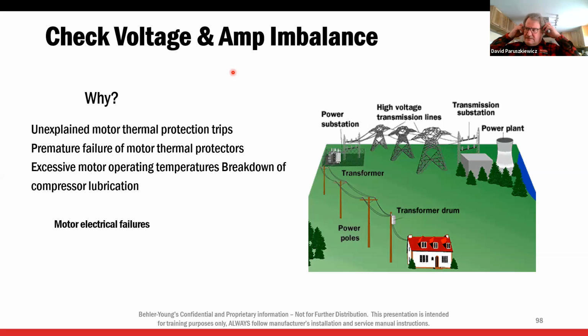Okay, so voltage and current imbalance. Now this, again, like I said, used to be we checked voltage and we're good, right? We got voltage. But with all the electronics, VFDs, ECM motors, economizer modules, voltage imbalance is going to lock things out now. If we have a bad voltage imbalance, the VFD can lock itself out. That ECM can lock itself out. So it's really, really critical to check our voltage imbalance and our amperage imbalance. Because if it's outside of allowable specs, we're going to have problems. We're going to have faults. And our whole goal here is to not ever come back, start it up, come back for maintenance, but I don't want other issues. So check your voltage imbalance. Check your amperage imbalance. In factories, a lot of times, especially with a wild leg, we'll have an amperage imbalance because there are more loads on the 110 legs than there are on the 208 legs, because all your lighting's on your 110, nothing's on your 208.